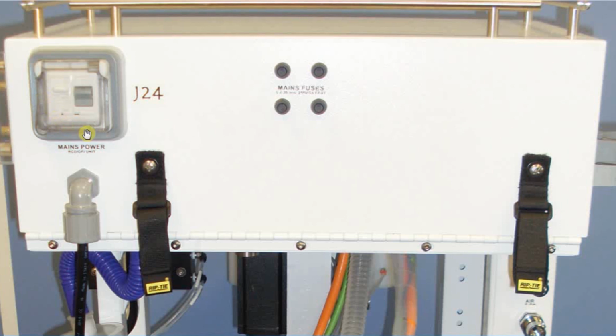To the left of that we have the RCD or residual current device, and this is the first point where the electricity goes into the machine, and if there's any problem with earthing or a power surge, this will trip out. So it's quite important when checking the machine or turning the machine on to make sure that this trip switch is not off, and make sure the green light is on, indicating that mains power has been fed to the machine. Because the machine will work adequately on batteries for several hours, it can become unnoticed that there's no actual mains power being delivered to the machine, and then you get a nasty surprise when the machine starts beeping at you that the batteries are low.